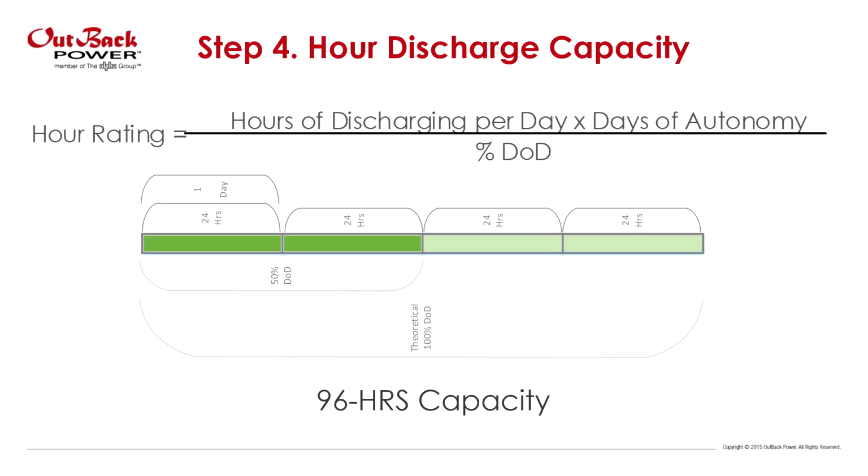All right, so we're going to take a side note. I won't go over this in very much detail, but we're going to talk about this for a little bit. Like I said, how fast you discharge your lead acid batteries will affect the capacity of your batteries. So what we need to look at is the hour discharge capacity. Understand how many hours we are discharging this battery and what capacity we will have that relates to those hours.